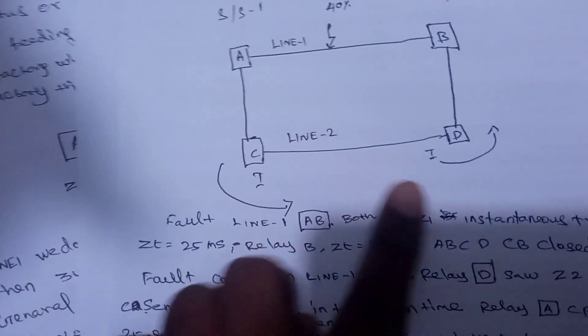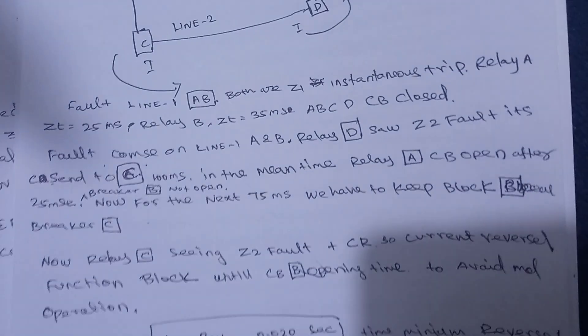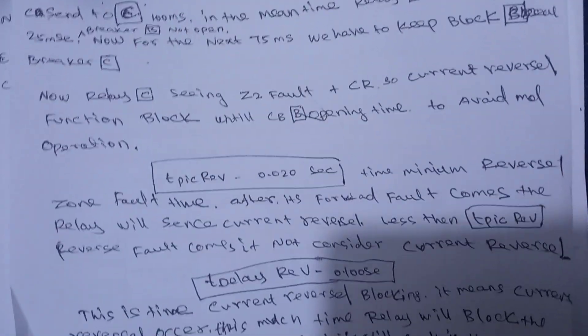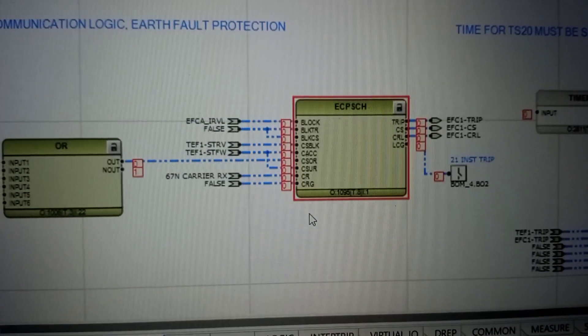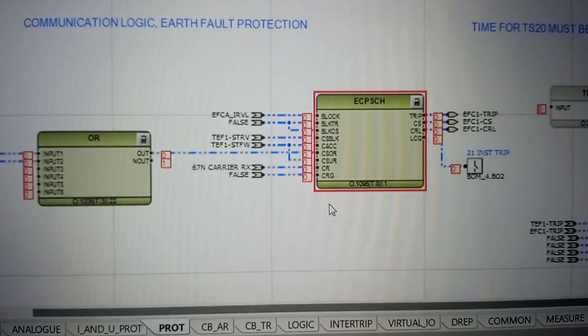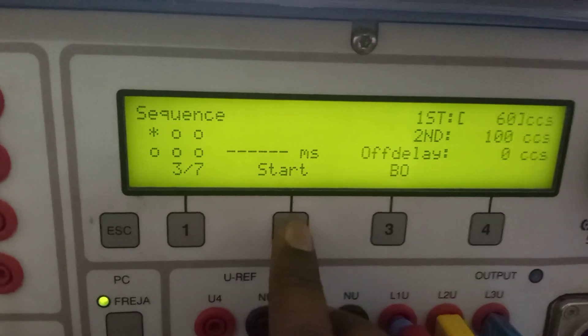Relay C is already monitoring for the reverse fault also, so it will cause an unwanted operation. You should read the theory — it is already written. Now we will check the function block of the communication scheme. I injected a reverse zone fault first, then a forward zone fault, and timing without carrier send, because I am not giving the carrier send command.